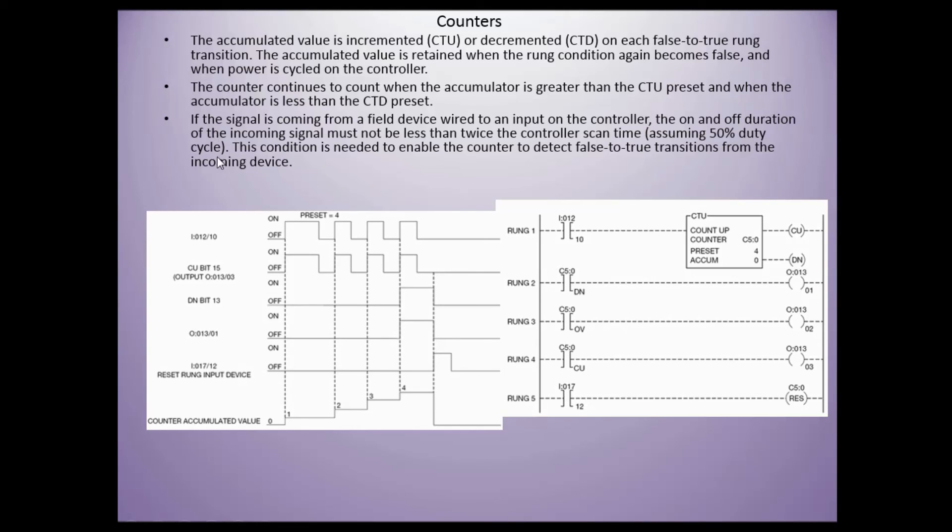If the signal is coming from a field device wired to an input on a controller, the on and off duration of the incoming signal must not be less than twice the controller scan, assuming 50% duty cycle. This condition is needed to enable the counter to detect a false to true transition from the incoming device. Keep that in mind if you have something you're trying to count that's very fast. This counter may not be able to do that for you.